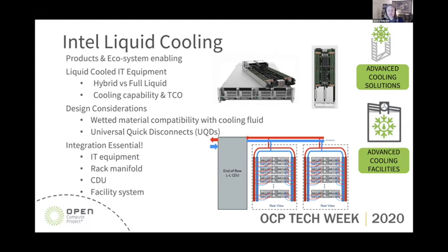One of the things that's essential here is really the integration. Yes, we can provide a part, but if you're talking about IT equipment, that's only part of the solution, only part of the cooling loop. We talked about the TCS cooling loop, the secondary loop or technology cooling system. You have the IT equipment, which needs to go into the rack manifold and then to the CDU, and then the CDU to the facility system. You need to look at it from a holistic point of view, not just buying components separately without considering the whole implementation. That's when a lot of people get into trouble. So that's my experience, and I'd like to hand it off to the next speaker.